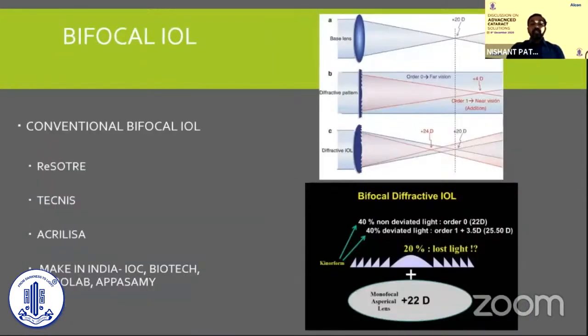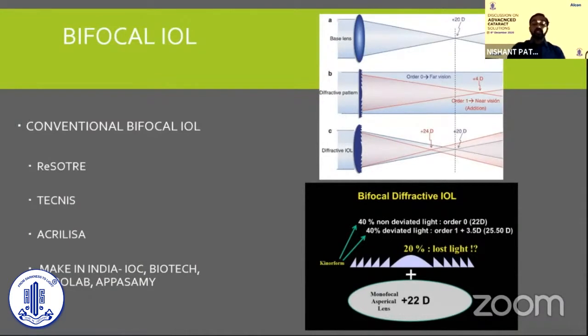In the primary basic bifocal IOL of diffractive design, you have diffraction at zeroth order and first order. The zeroth order accounts for about 40% of light, which is non-deviated and dedicated for distance vision. The remaining 40% for the first order is deviated for near vision. Importantly, 20% of the light is lost — and this is what we focus on when moving to trifocal IOLs, because this lost light is what causes visual disturbance.